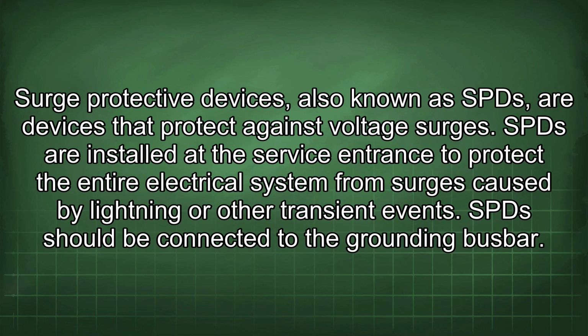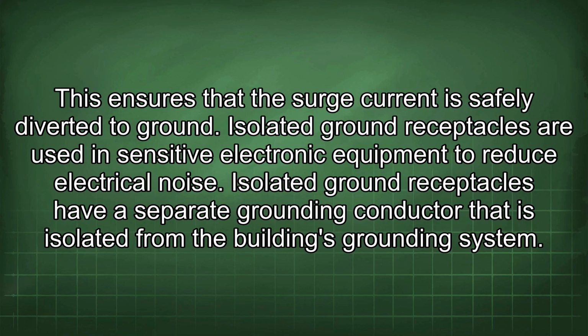Surge protective devices, also known as SPD, are devices that protect against voltage surges. SPD are installed at the service entrance to protect the entire electrical system from surges caused by lightning or other transient events. SPD should be connected to the grounding busbar. This ensures that the surge current is safely diverted to ground.